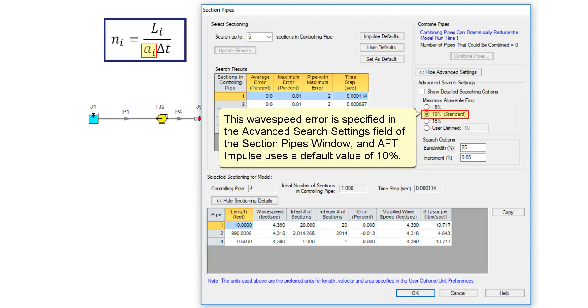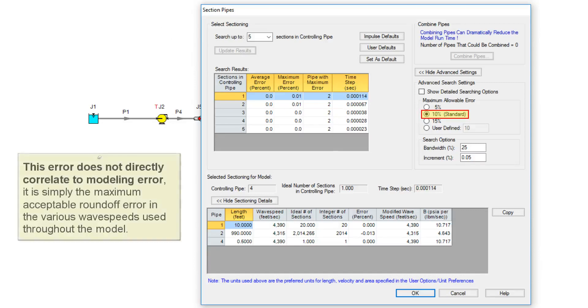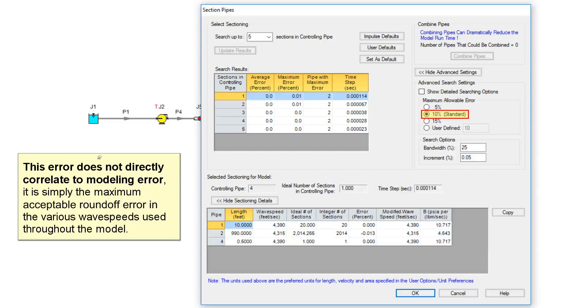The traditional approach is to recognize that the wave speed is the least certain parameter and to allow an error in wave speed to be introduced up to 15%. The wave speed error is specified in the advanced search settings field of the section pipes window, and AFT Impulse uses the default value of 10%. This error does not directly correlate to modeling error. It is simply the maximum acceptable round-off error in the various wave speeds used throughout the model.